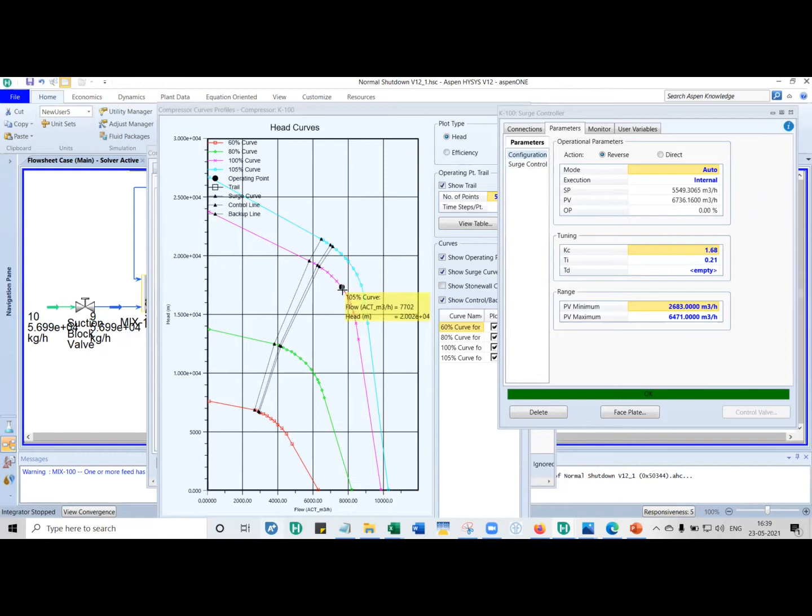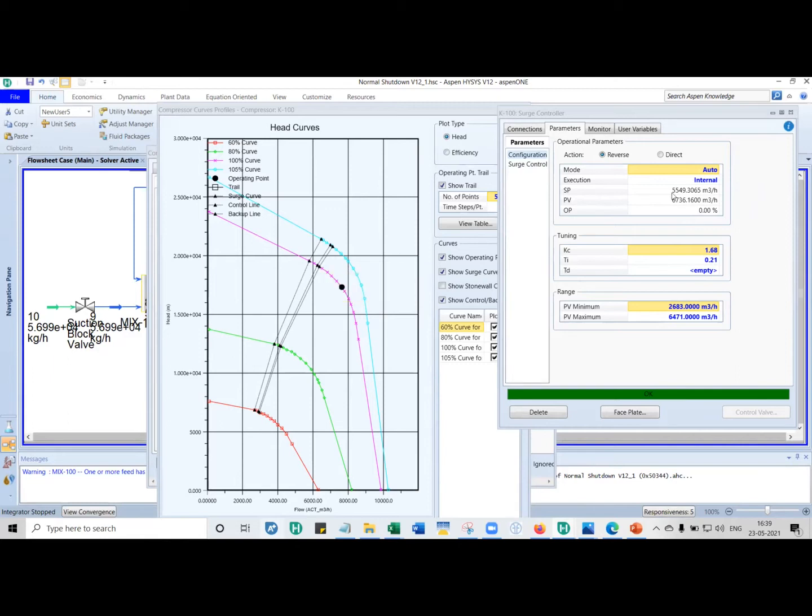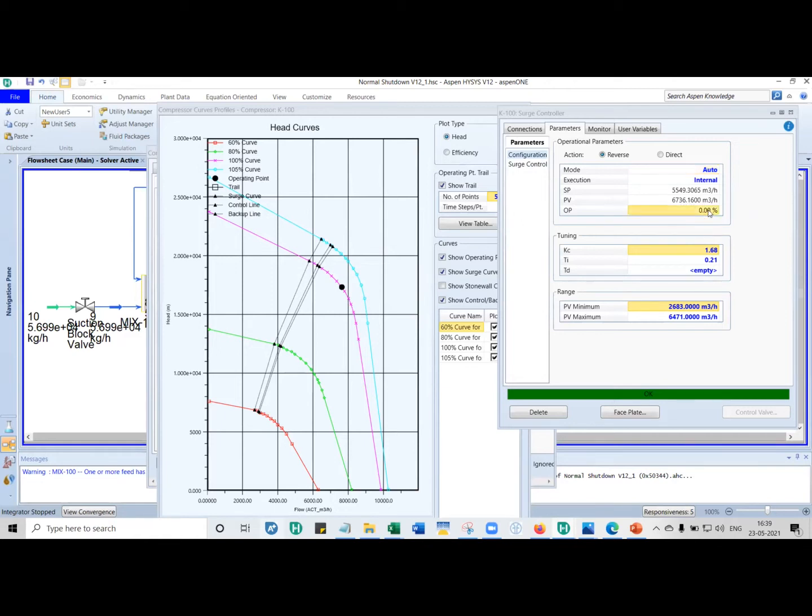So let's say the operating point touched the surge control line. What the anti-surge controller is doing is it estimates how much flow should I recycle? If I have to recycle so much flow, how much should I open the anti-surge valve? That is what this is doing.